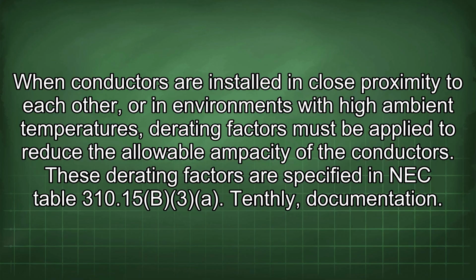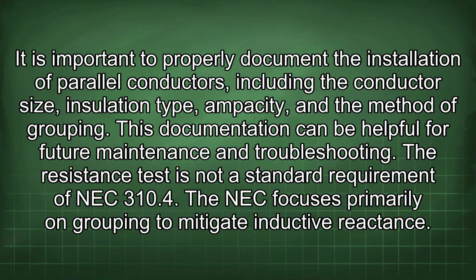These derating factors are specified in NEC Table 310.15(B)(3). Tenthly, documentation. It is important to properly document the installation of parallel conductors, including the conductor size, insulation type, ampacity, and the method of grouping. This documentation can be helpful for future maintenance and troubleshooting.